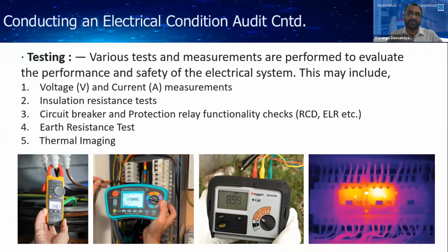Then the insulation test. That means you can test whether the circuits have a good insulation resistance level. All these tests can be done during the condition audit, and you can learn how to do them there. I am just telling you now what the tests are and how to do them, so you can experience it later. Then the circuit breaker protection and relay function test. That means you can check whether the RCDs of the systems are working properly and the protection relays are working properly.